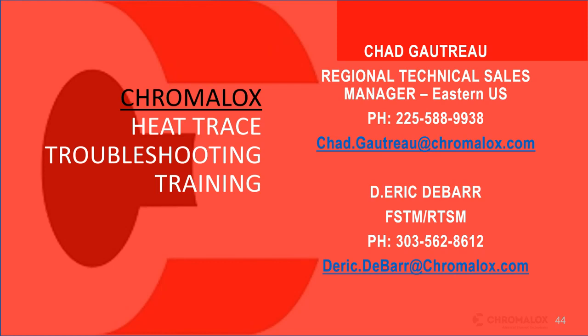I don't know what you mean by wind exposure, because if the RTD is mounted underneath the insulation, it shouldn't be exposed to wind. If you are having some issues and you'd like to install a secondary RTD, you could do that down the line. It's not a standard practice, but I have seen instances where, if you're having trouble with a line, maybe a second RTD gives you a different option.